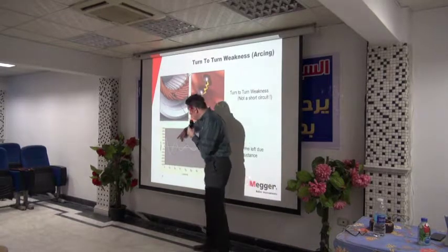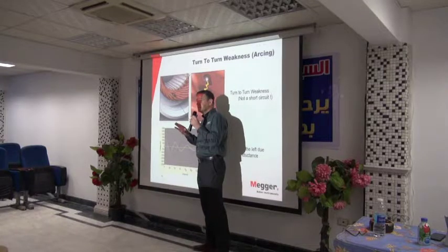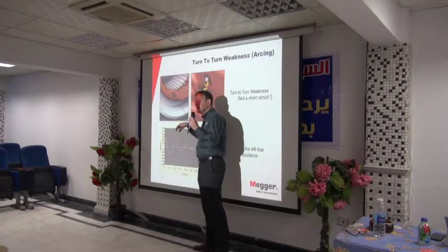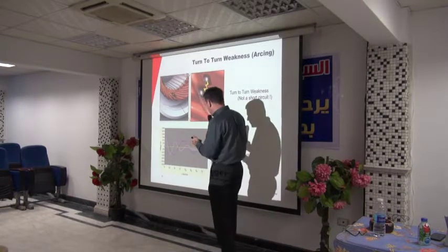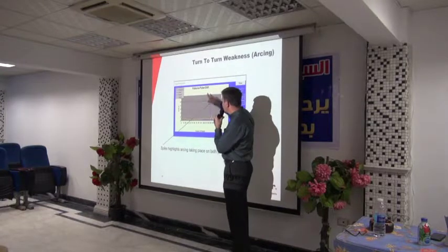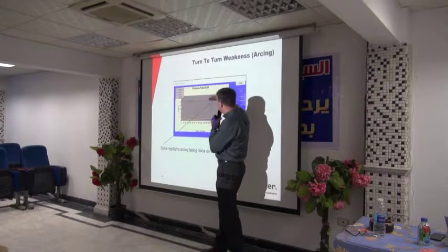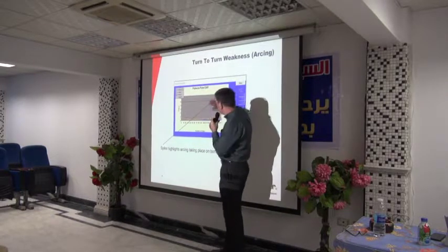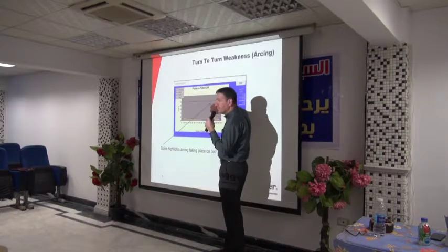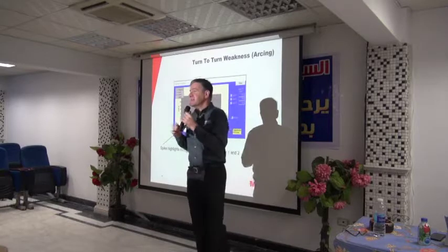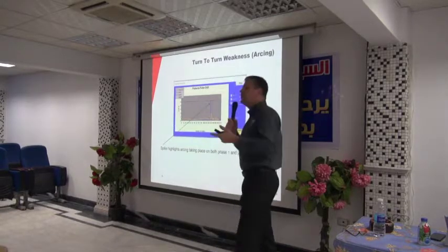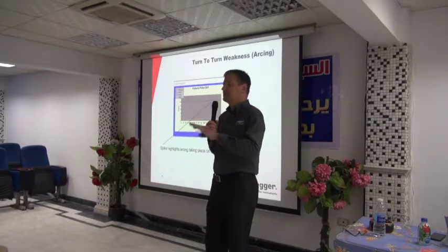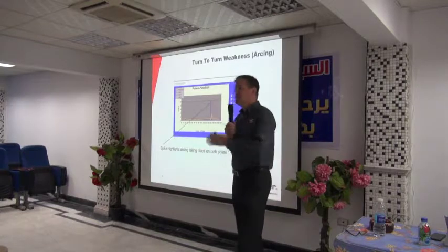Okay, so we compare how much the waveforms are separated. So we have two tolerances. One is called line to line, and we compare the area separation. And the second one is this one, pulse to pulse EAR. This is a tolerance. So if this breaks through the line, the test will stop automatically. But even though this has not broken the line, this is still a problem. So it's basically how we analyze the data. When we sell equipment, we give training on how to analyze and how to use. That's quite a big subject, but basically that's what it means.